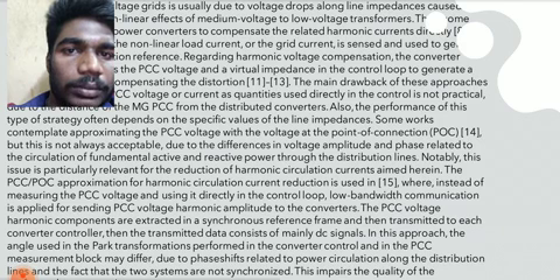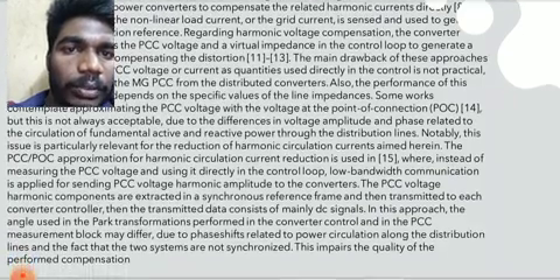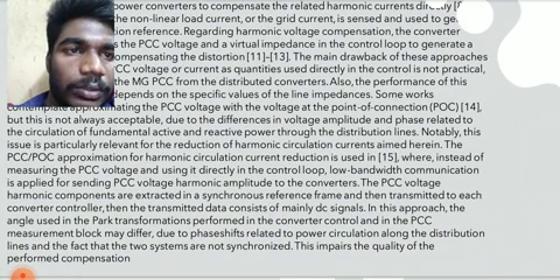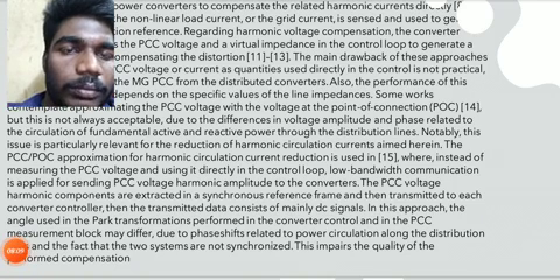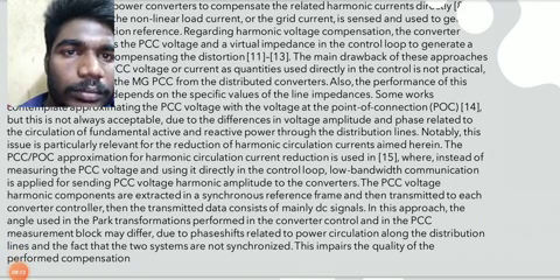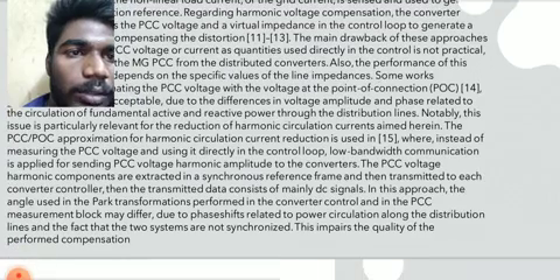Some works contemplate approximating the PCC voltage with the voltage at the point of connection, POC, 14, but this is not always acceptable due to the difference in the voltage amplitude and phase related to the circulation of fundamental active and reactive power through the distribution lines. Notably, this issue is particularly relevant for the reduction of harmonic circulation addressed herein.